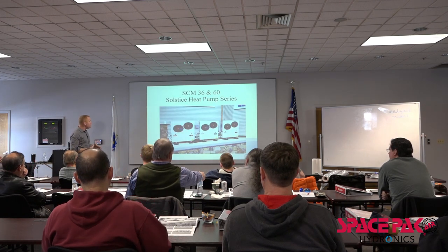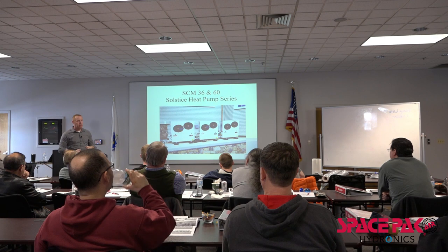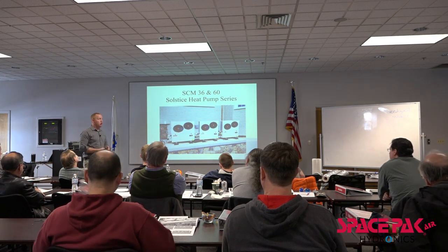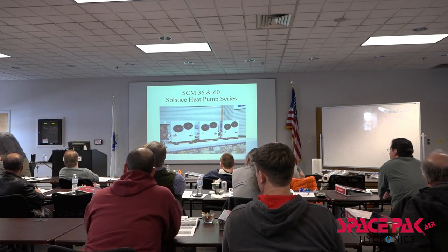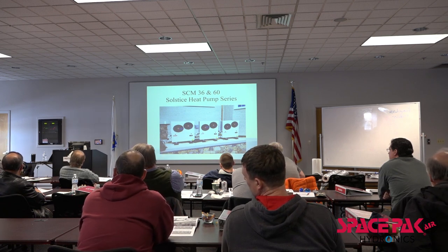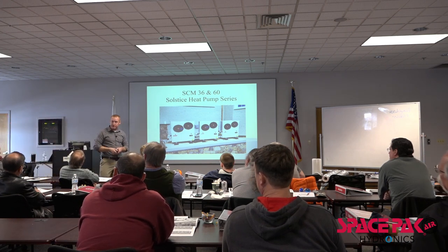Right? So our Solstice series of heat pumps, our SCM series, are the ones designed for primary cooling, right? They'll deliver cooling temperatures down to negative 20 outside ambient, okay? We can't see it from here. Actually, yes, you can. On that brick building across the street, there's a unit up there, an SCM unit, that cools our server room year-round for the offices across the street.